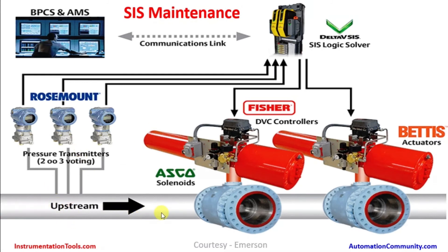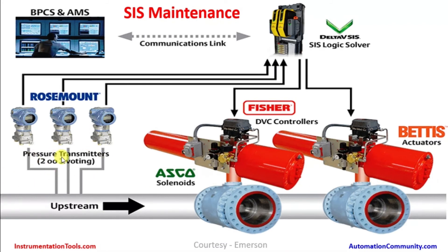Consider a piping system with two on/off valves and pressure transmitters measuring process pressure, all connected to the SIS logic solver in a two-out-of-three (2oo3) voting configuration. The logic solver senses signals from three transmitters; whenever any two transmitters signal high pressure — in combinations A&B, A&C, or B&C — the logic solver commands the valves to close. This is the two-out-of-three voting logic.